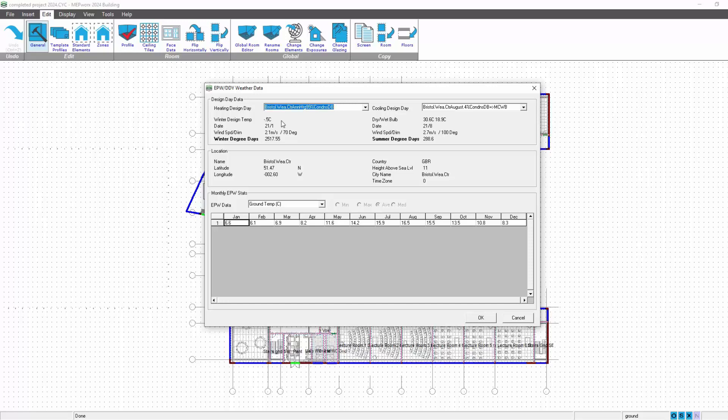It will allow you to look at glazing gains in the winter. Obviously, to date, the software has only looked at June, July, August, September, the peak months for cooling, but it does actually allow you to look at cooling loads in the winter. If you, for example, have a glazed facade with an overhang where the overhang protects the glass in the summer because the sun is higher in the sky, in the winter the sun's lower in the sky, you might actually get a larger glazing gain in the winter. This allows you to make one or two more detailed assumptions and perform more detailed calculations. So that's the Energy Plus data being used and this is the reviewing of all the data that's provided with the weather information. Moving into the energy program, things are a little bit different.